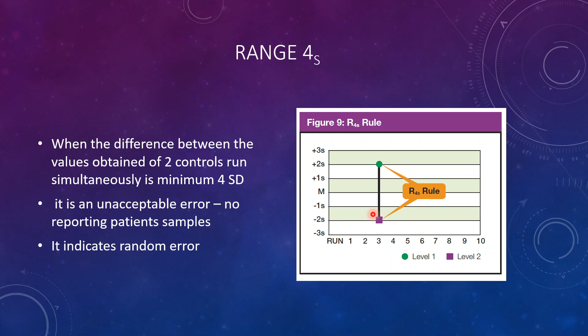Now if you look at the previous one, you have only one control running on each day, day 4, day 5. But here, on one particular day, two controls are run. If you find that the difference between the two controls is 4 SD, 1, 2, 3, 4, a 4 standard deviation difference between the two controls run simultaneously, then this is a violation of rule R 4s. This is again an unacceptable error and no reporting for that particular analyte is to be done. This indicates a random error.